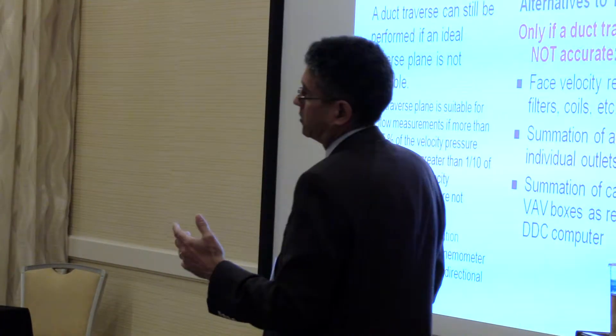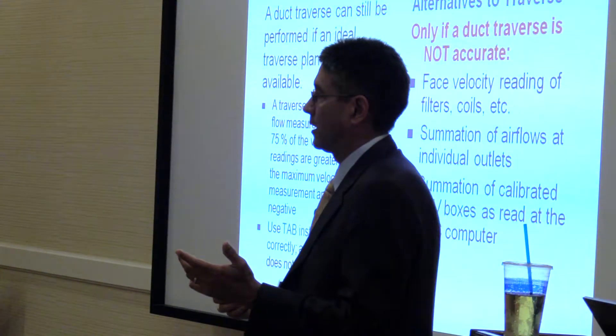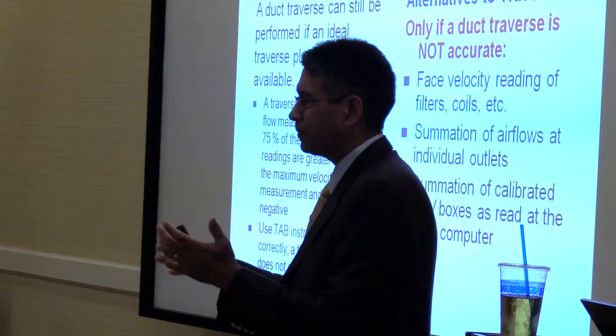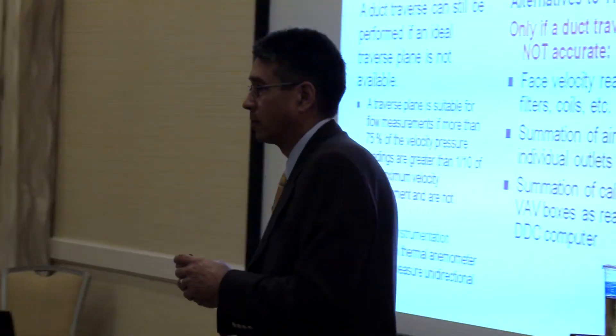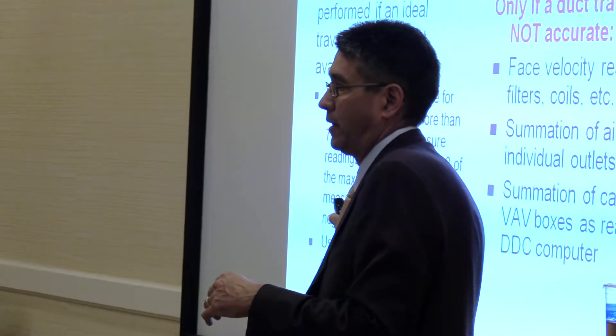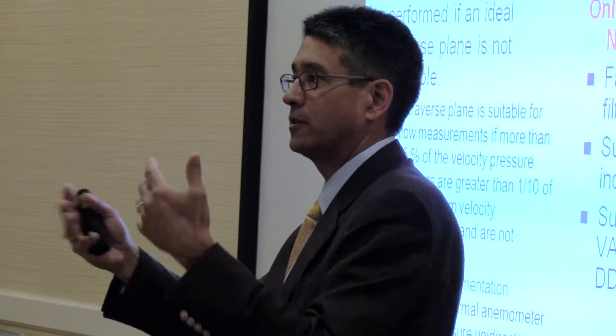A lot of times we'll go ahead and take one and see what it says. It might come out showing a lot of zeros, a lot of negatives, air hugging one side — we cannot get a good measurement here. Always try it. A lot of times this comes back to the TAB tech using his instrumentation properly and using his judgment, and reporting the velocity profile so you can see it was a good traverse.